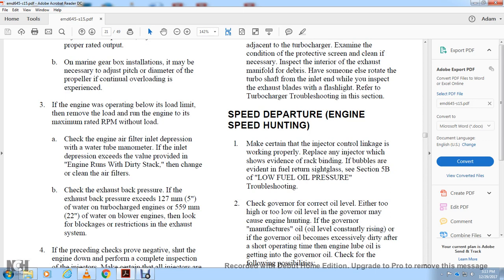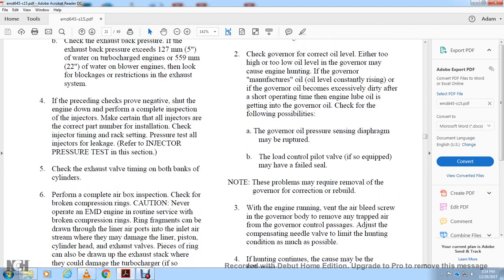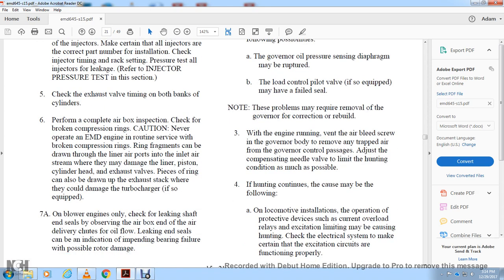Check the governor for correct oil level — either too high or too low oil level can cause the engine to hunt and the governor to lose control. Over operating time the governor oil can become dirty, and if engine lube oil is entering the governor, check for a ruptured governor oil pressure sensor diaphragm. The load control pilot valve may have failed. The problem may require removal of the governor for correction or rebuild. The governor compensating needle valve can be adjusted to limit hunting conditions.